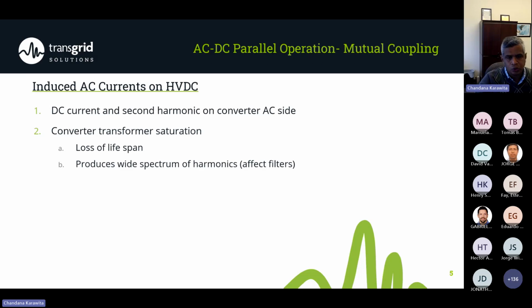So what are the issues with the AC current on the DC? When we have a 60 hertz component on the DC side, this will modulate into a DC current and a second harmonic on the AC side. That means the converter transformer will see some DC current and the second harmonic appearing at the converter side. The main issue this leads to is transformer saturation.